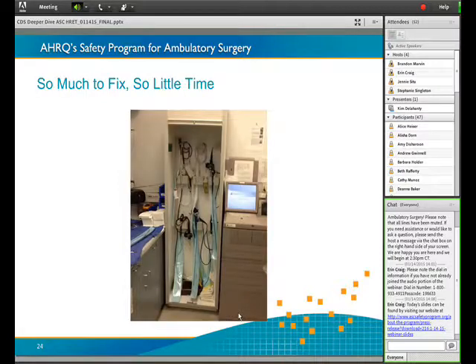Okay, so much to fix, so little time. This is a scope cabinet, and what's wrong here is that the scopes have to be free hanging, not touching anything, not the cabinet, not each other, and should not have any sheaths on them. They were trying to do the right thing with this plastic sheath, but unfortunately it causes moisture, and with moisture and heat, bacteria or microorganisms grow. It should be in a well-ventilated cabinet, not jammed up.